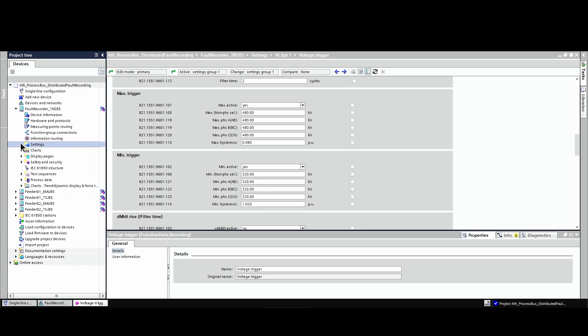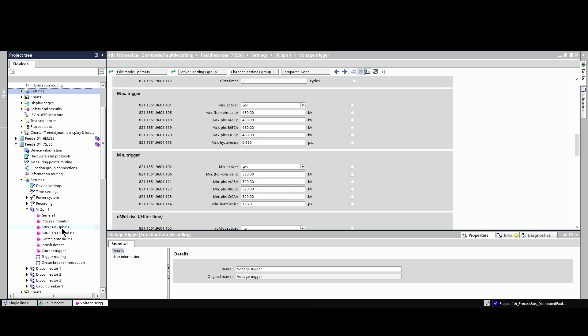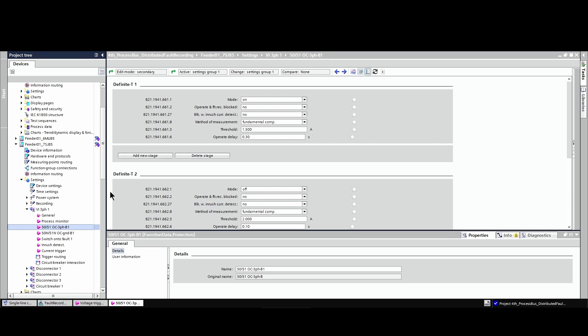Now let us look inside protection relay 7SJ85 for feeder number 1. Here in the settings chapter, voltage current 3-phase number 1, overcurrent circuit breaker. Here are the settings of the trip which operates above 1.5 amps secondary, which will cause a trip and operate inside the protection relay. Later on, we will see in the information matrix that this indication will be used to start the fault recorder in the 7KE85.